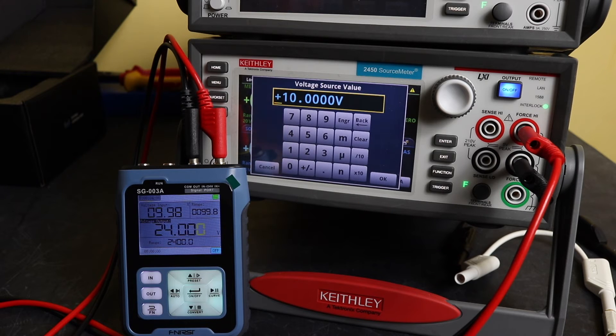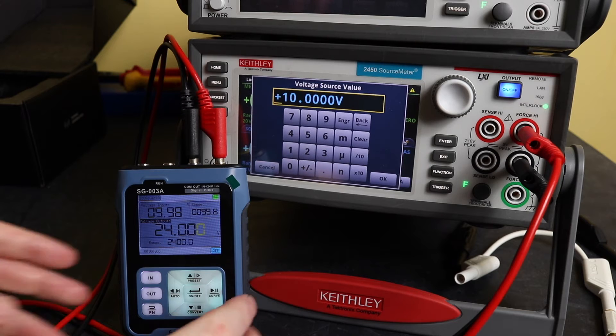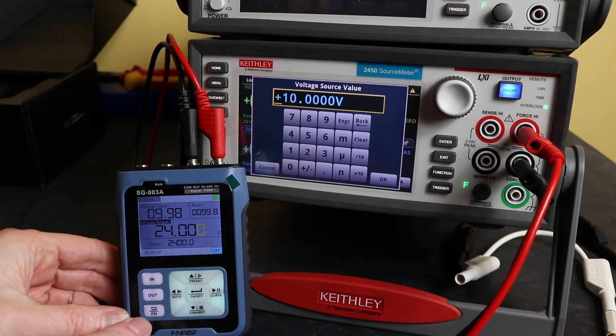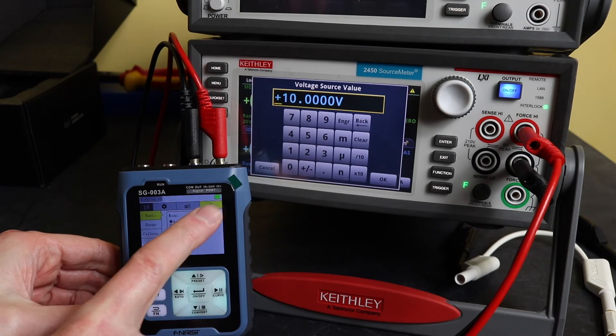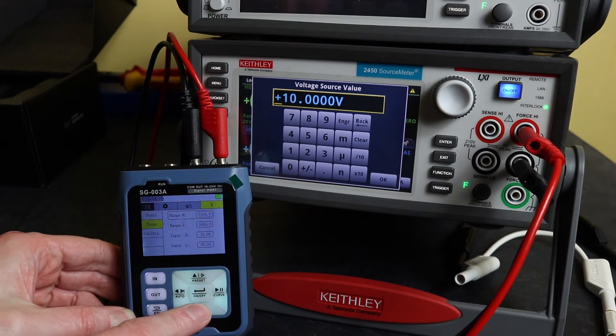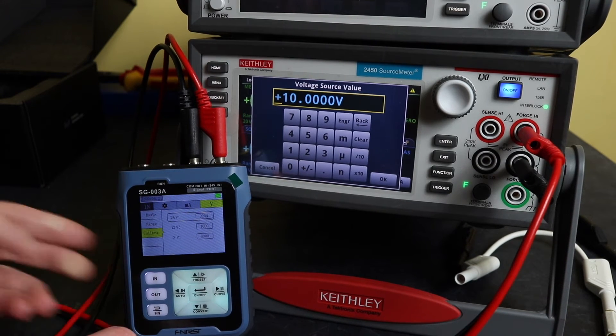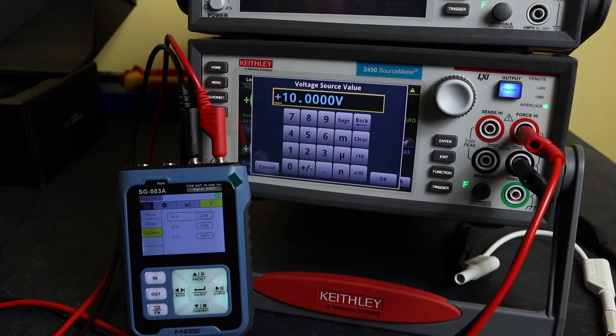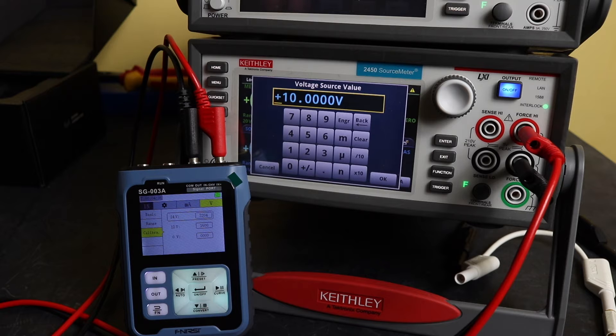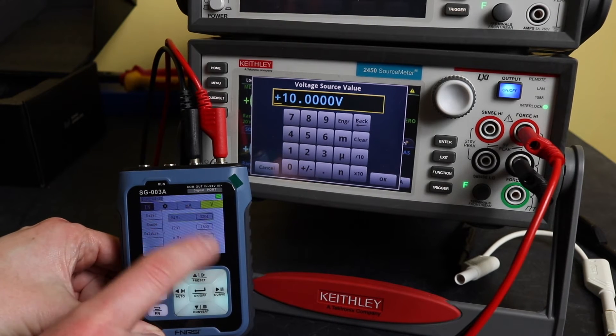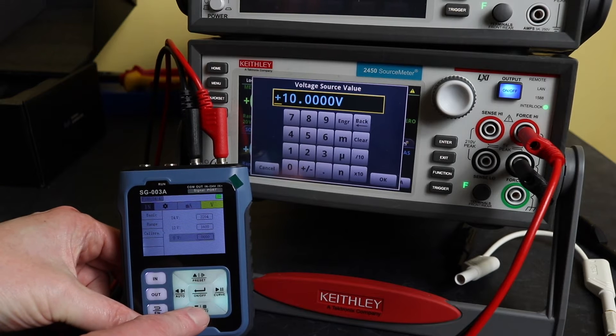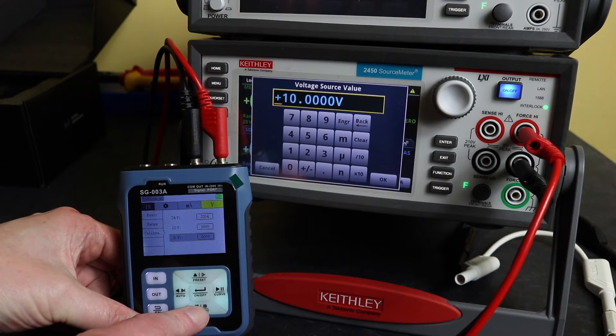The constants themselves are easy enough to adjust. You have to go back to the function button and input. We're on the volts tab up there and here we can scroll down to the calibration and I've got three settings here, we've got 0, 12, and 24 volts. So there are two ways to adjust these. Once you've gone to that window, hit the enter.